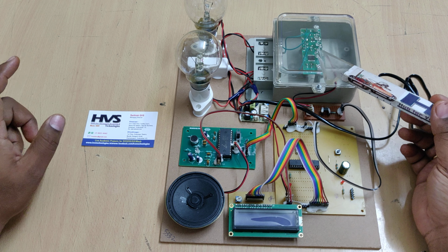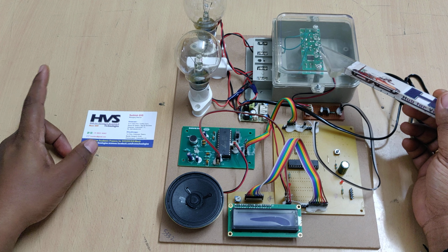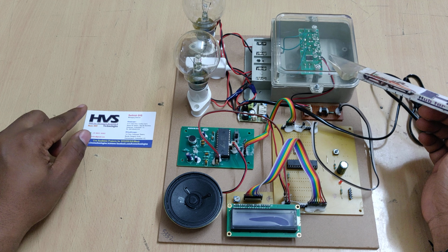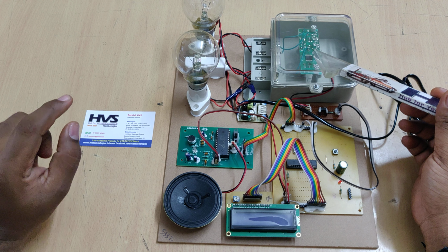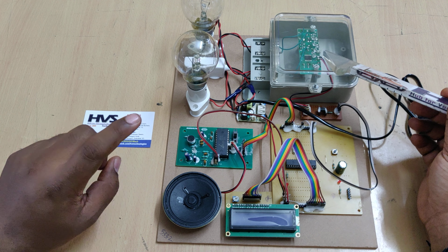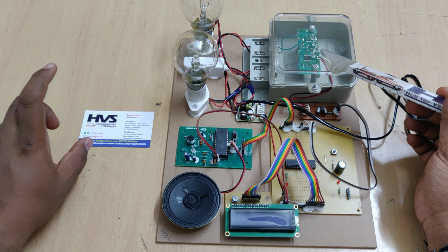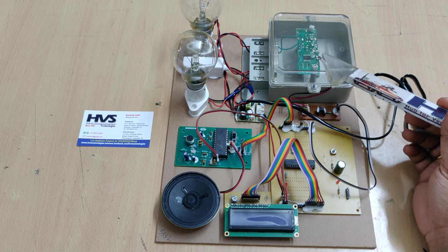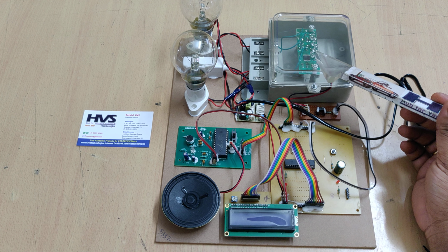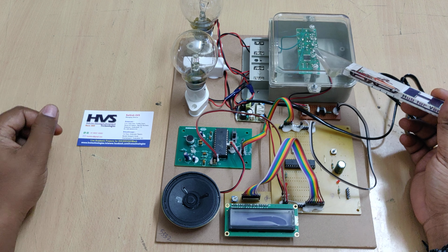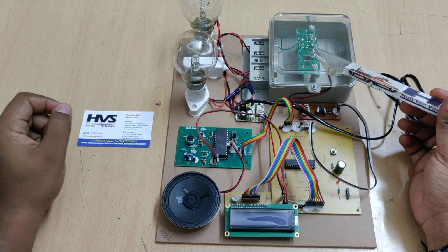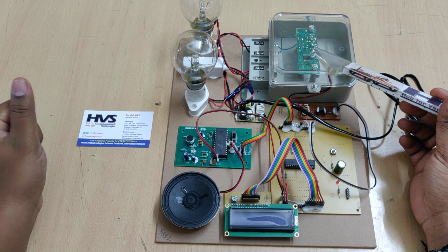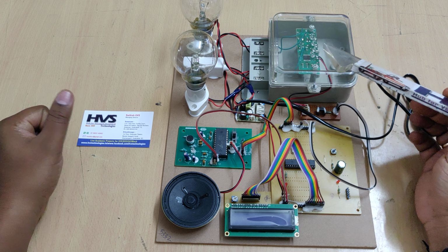So whenever the LED completes 3200 blinks, it is considered as 1 kilowatt hour. Means if it blinks 3200 times, that's equal to 1 kilowatt hour, meaning 1 kilowatt of energy consumed by the load in that duration. And next, to calculate the load, if the LED blinks once per second, it indicates that 1000 watts of load is connected. So this is the calculation part.